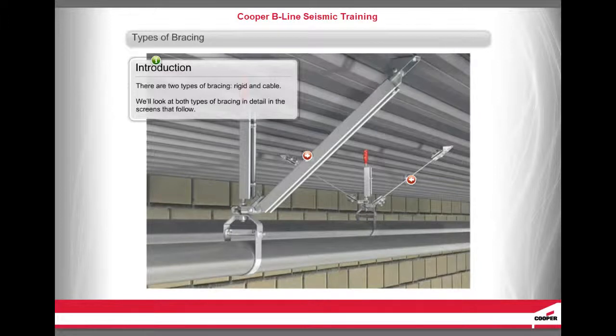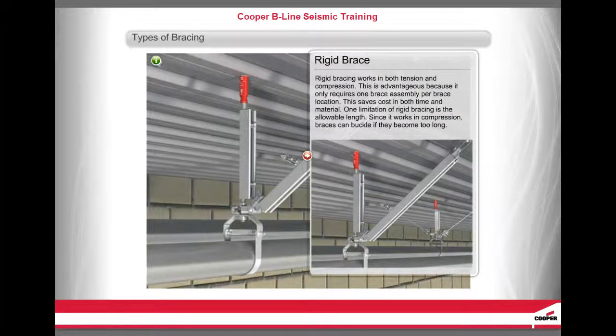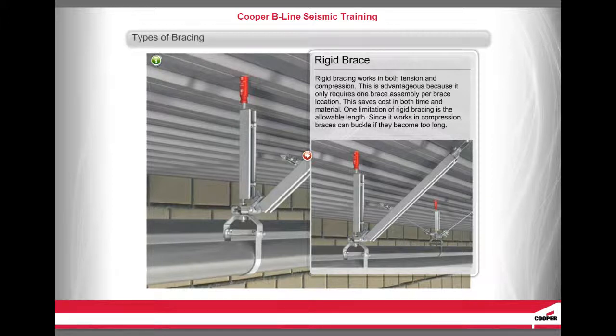There are two types of bracing: rigid and cable. Rigid bracing works in both tension and compression, which is advantageous because it only requires one brace assembly per brace location, saving cost in both time and material. One limitation of rigid bracing is the allowable length — since it works in compression, braces can buckle if they become too long.